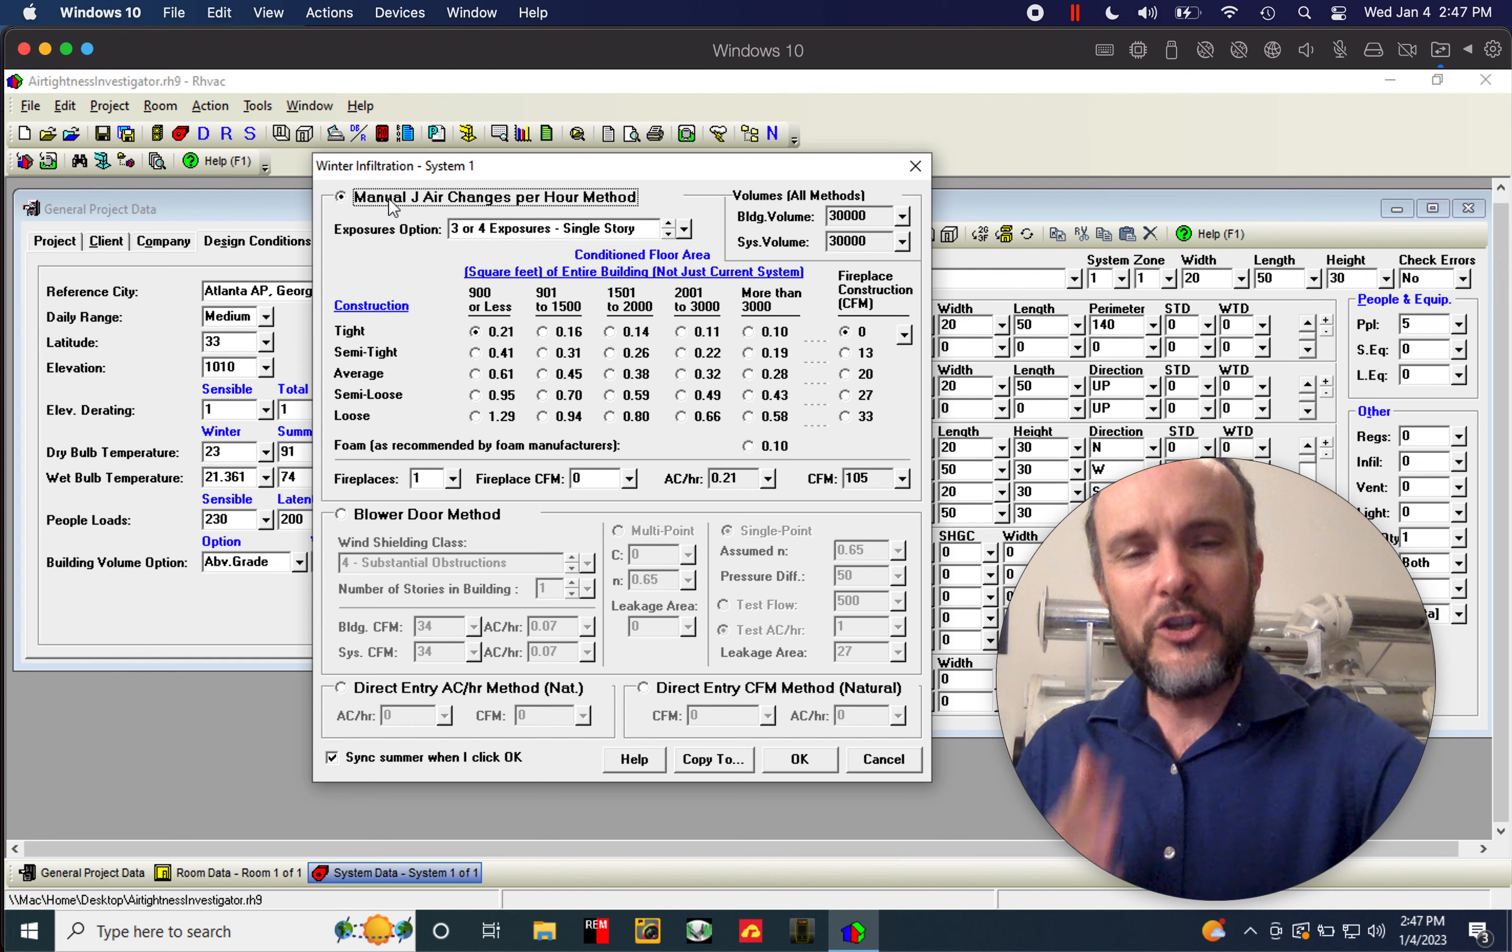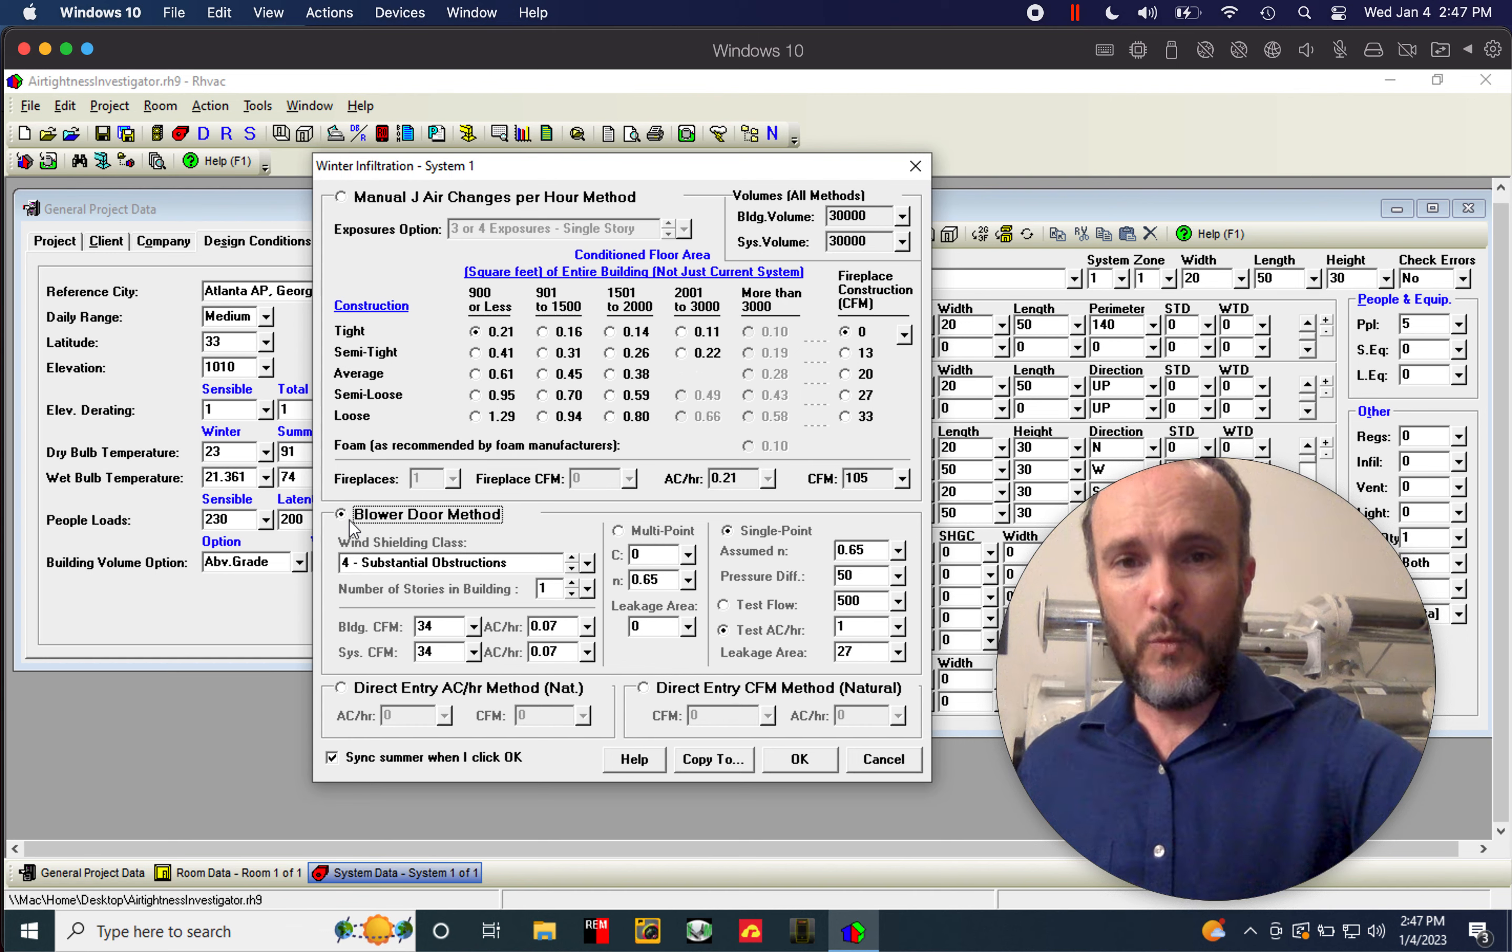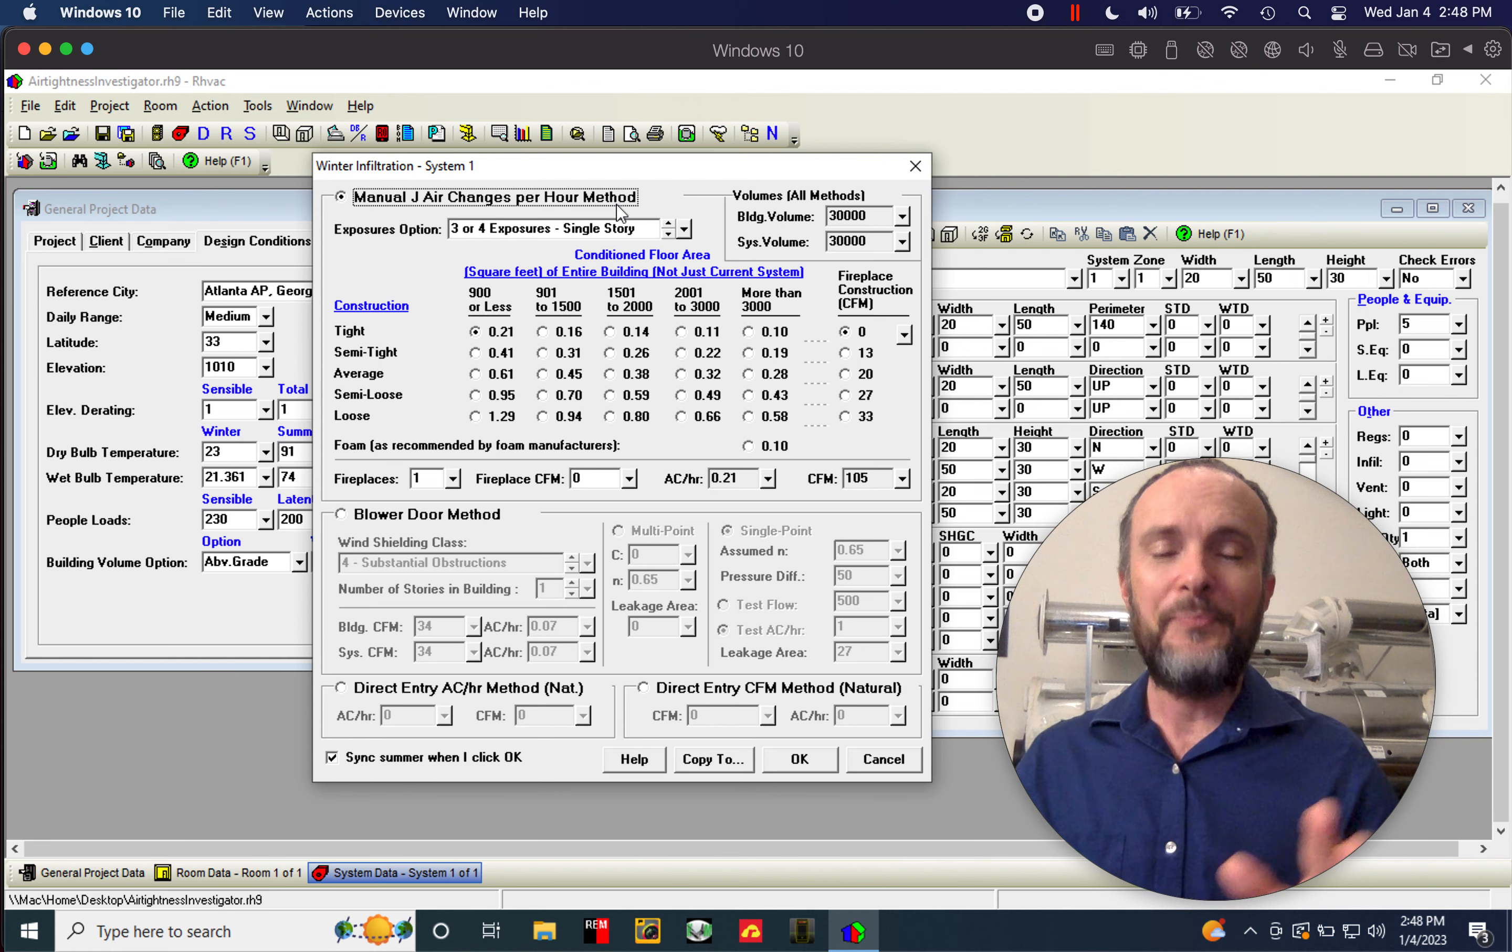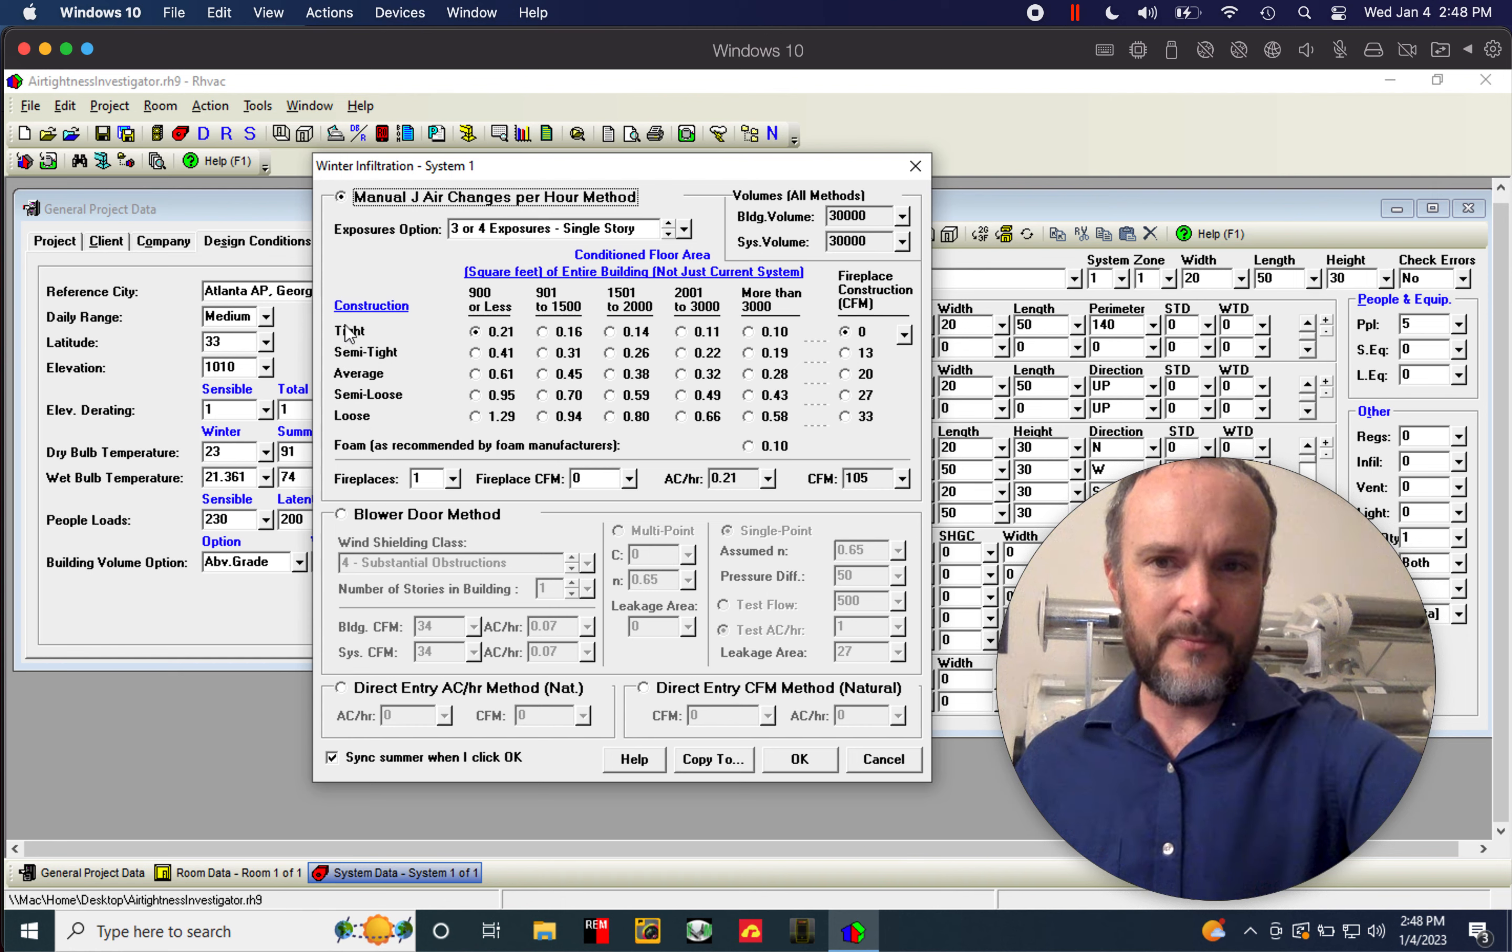But you have two options here. The top half of this screen says Manual J Changes Per Hour Method. And on the bottom, you've got Blower Door Method. We are going to start with the Manual J Air Changes Per Hour Method. And by the way, the word air changes is very confusing in HVAC, so we're not going to deal with that right now. But just suffice to say, what we're talking about here is the actual air exchange from outdoors to indoors through air leakage in the skin of the home. So we've got this chart right here, which is basically tight, semi-tight, average, semi-loose, or loose.